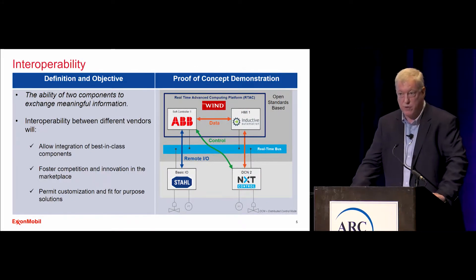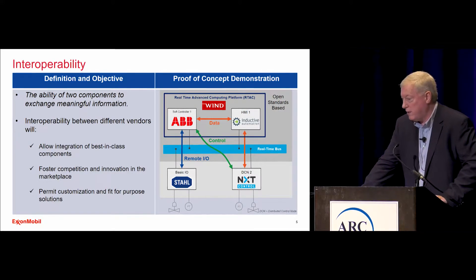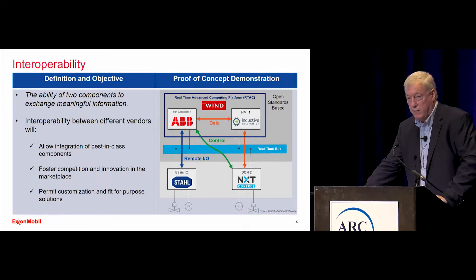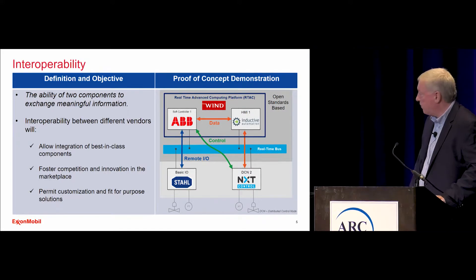We created a control algorithm using a soft controller from ABB and a hard controller DCN from NXT Control. We used some basic I/O from STAHL and integrated it with the Ignition graphics from Inductive Automation. There are no translators or gateways — it communicates using OPC UA and DDS, and we used the IEC 61499 and IEC 61131 standards for programming. All standards-based.